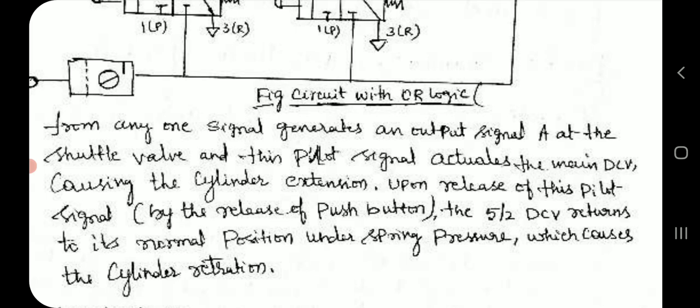From any one signal generates an output signal at the shuttle valve and this pilot signal actuates the main direction control valve causing the cylinder extension. Upon release of this pilot signal by the release of push button, the 5/2 direction control valve returns to its normal position under spring pressure which causes the cylinder retraction.